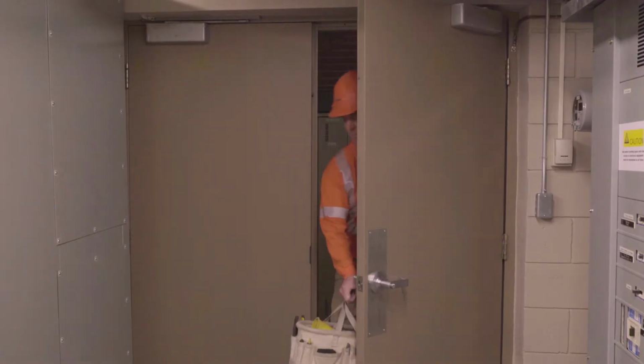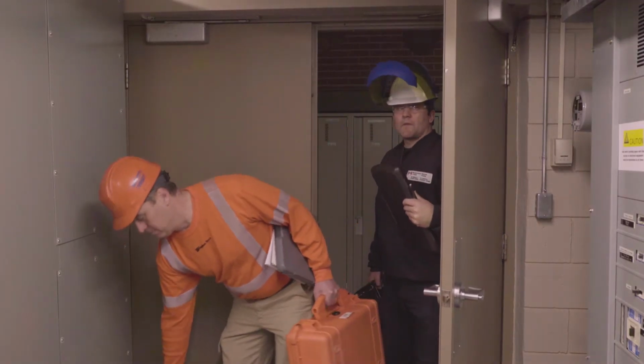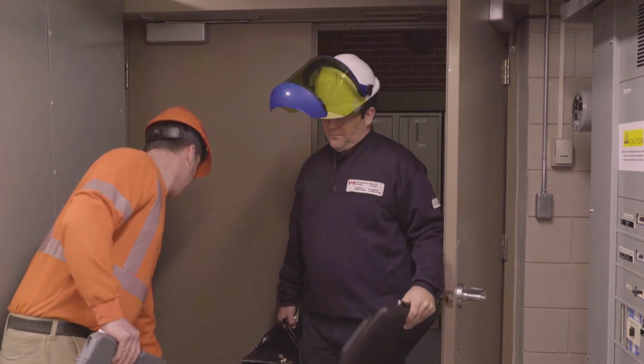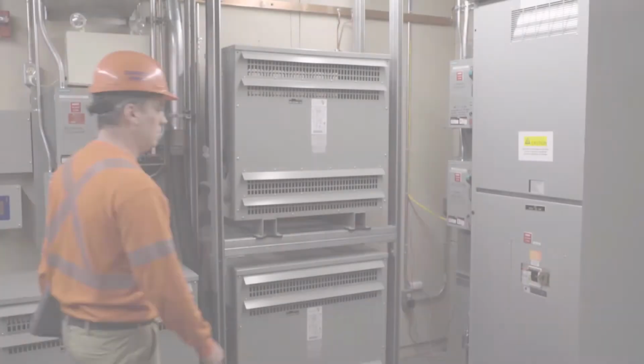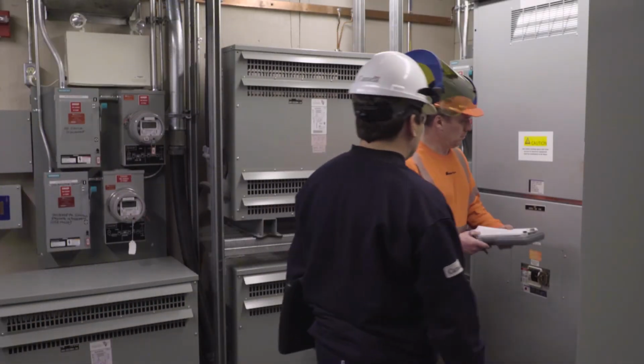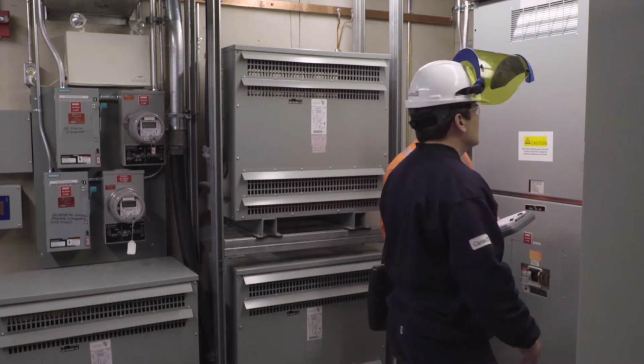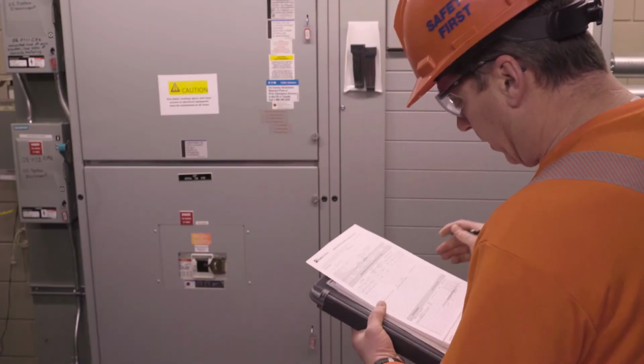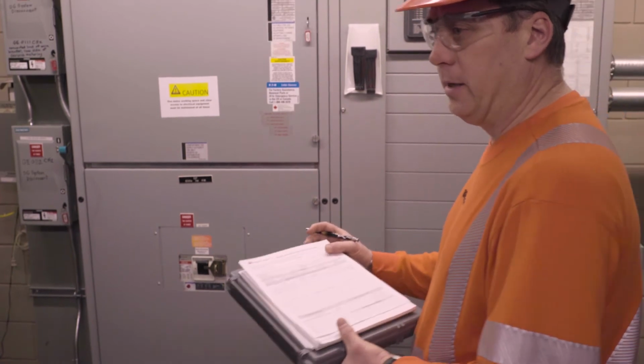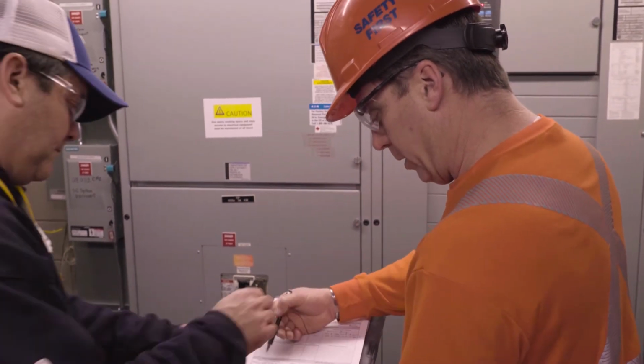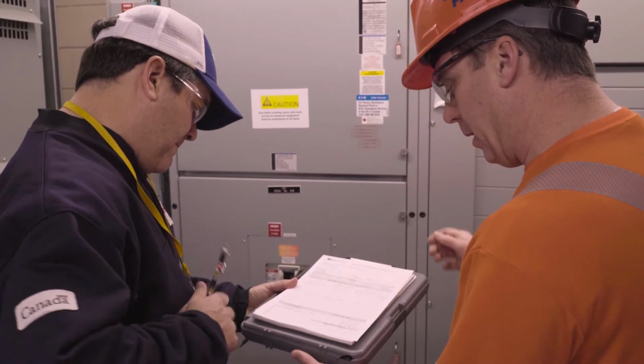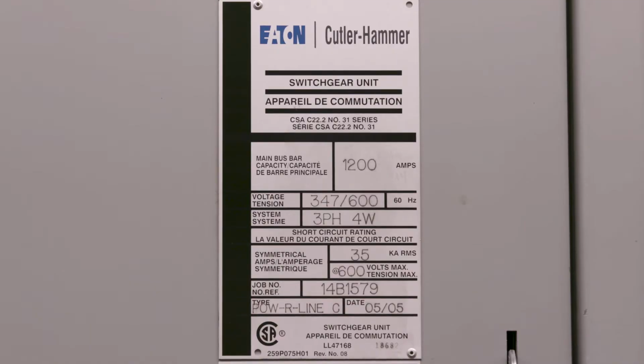Static testing an electrical metering installation provides Measurement Canada inspectors with a step-by-step process that will ensure they are completely aware of their surroundings. It also helps inspectors identify any possible safety issues related with the electrical service or equipment, and to verify that the service is within their qualifications and rated under 750 volts.